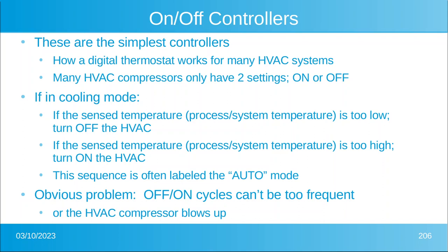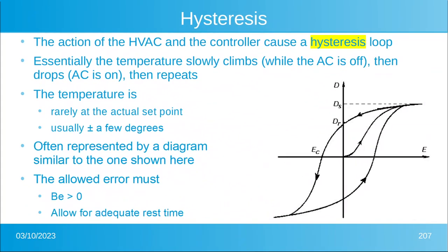There's more going on than first meets the eye. The on/off cycles can't be too frequent or the compressor blows up. So the compressor lets your house warm up a little, turns on, cools it down below the set point, turns off, and waits. Engineers call that hysteresis.